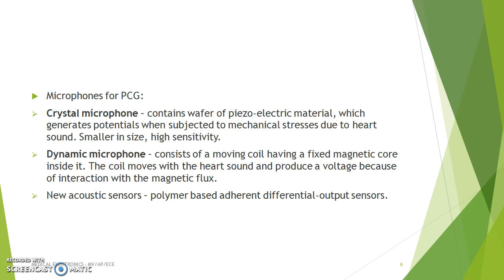While recording PCG, we use a microphone setup. The conversion of heart sounds into electrical signals can be done using a variety of transducers, primarily microphones. We classify microphones into two types. The first is the crystal microphone, which contains a wafer of piezoelectric material that generates potentials when subjected to mechanical stresses due to heart sound. It is very small in size but has high sensitivity. The second is the dynamic microphone, which consists of a moving coil with a fixed magnetic core inside. The coil moves with the heart sound and produces a voltage due to interaction with the magnetic flux.